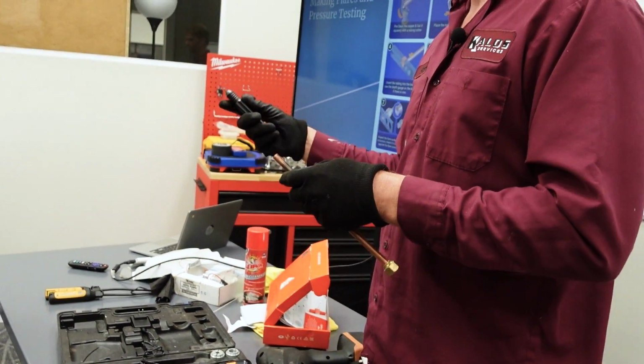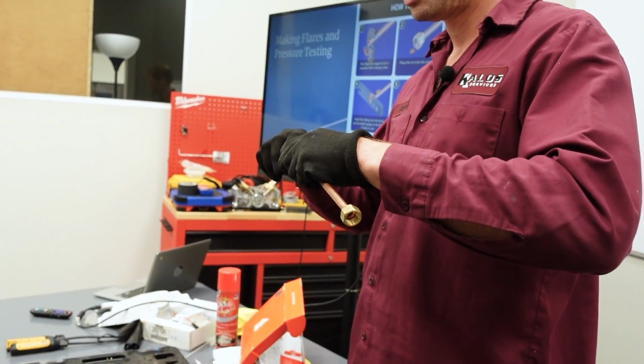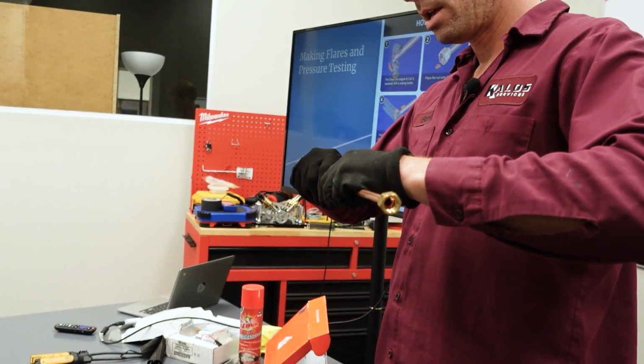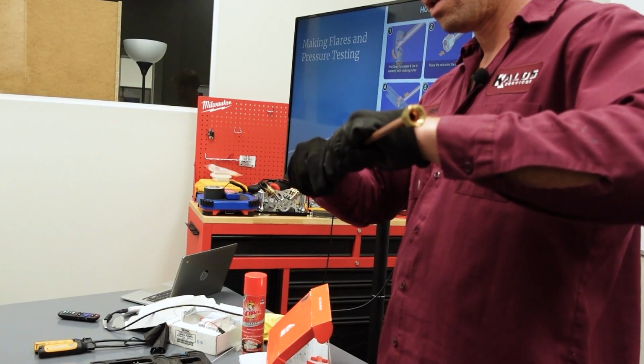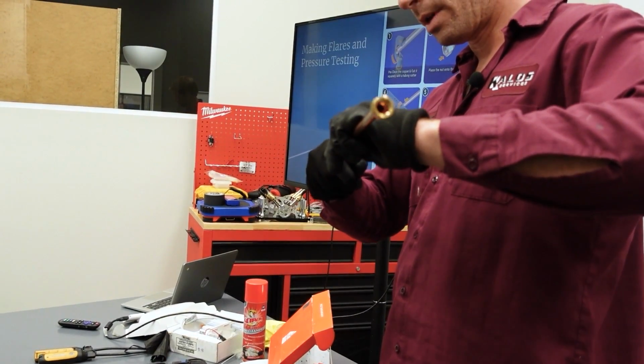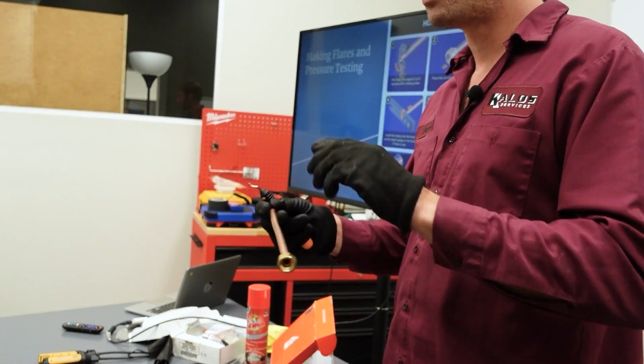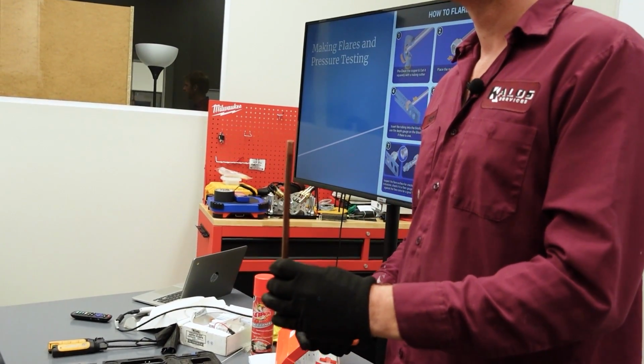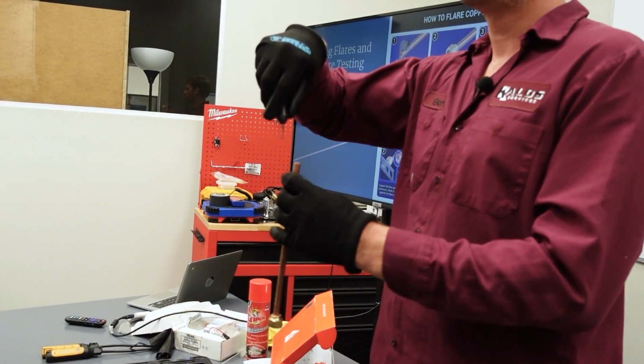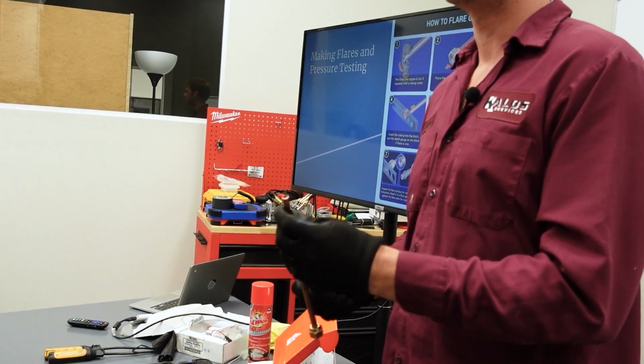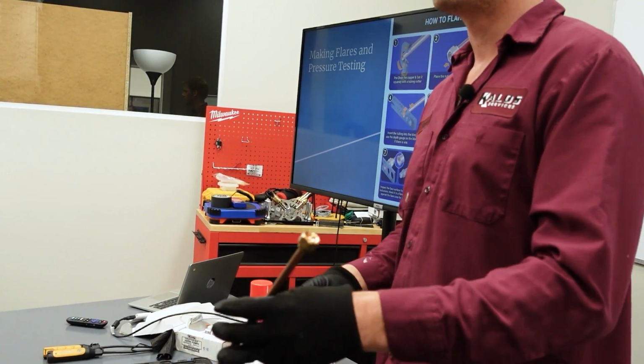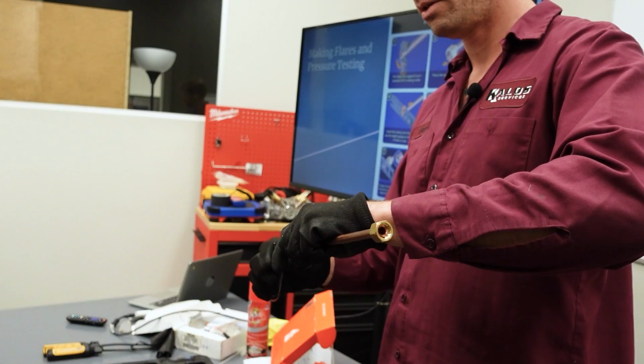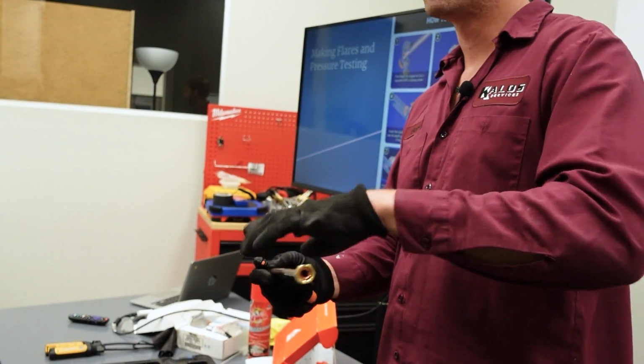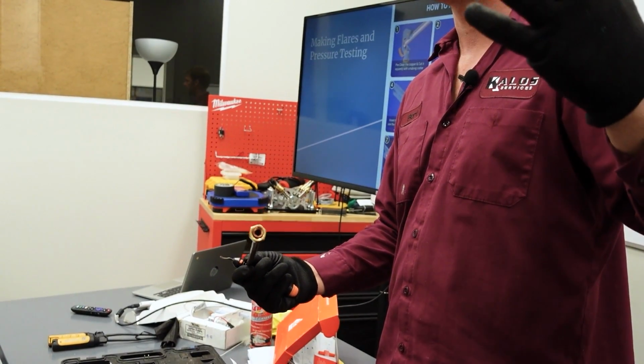So that's where the deburring tool comes in - you have to go in there and cut out that lip. Take your time on this, paying attention to what you're doing. If your copper is sitting flat and you start using the tool, little bits are just going to fall straight down inside, so you want to adjust your copper to have a little bit of a downward angle, keeping in mind there's usually a line set attached to it.